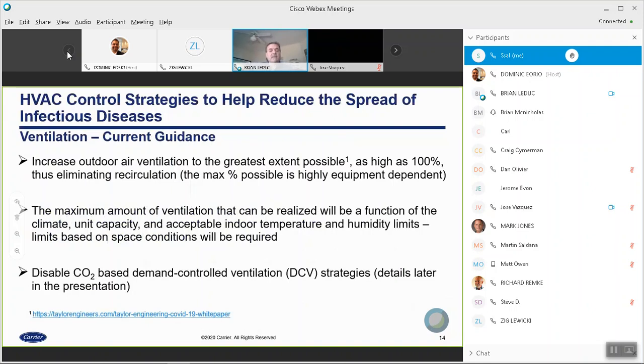Now, obviously, you're not going to be able to go to 100% in most pieces of equipment because it is not sized for 100% outside air on a design day. But the recommendation is to increase ventilation to the greatest extent possible. The maximum amount that can be realized, again, is going to be a function of the ambient conditions at any given time, the unit capacity, and the acceptable indoor temperature and humidity limits, which is really going to tell you how far you can go with ventilation, your ability to maintain temperature and humidity.